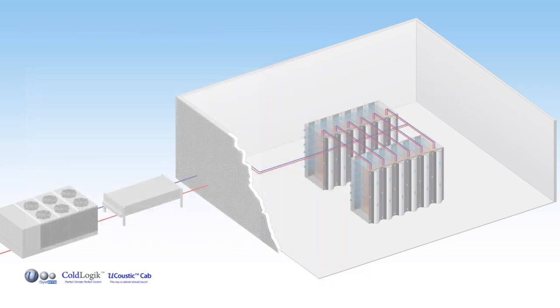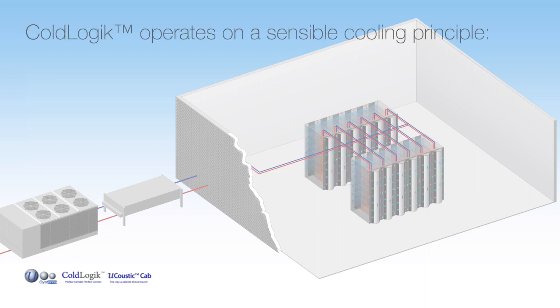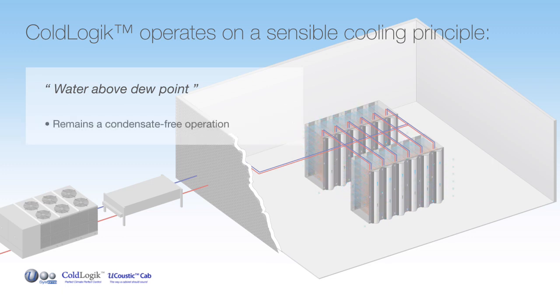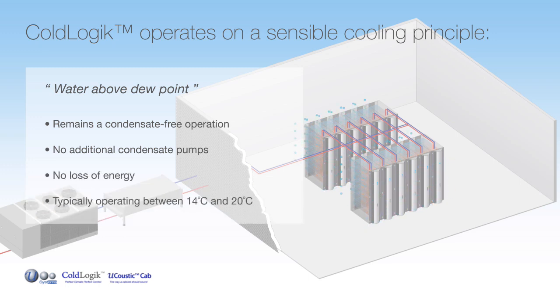The entire ColdLogik system operates on a sensible cooling principle, that is to say, water above dew point, ensuring that the system remains a condensate-free operation, so there are no additional condensate pumps and no loss of energy. Typically operating between 14 and 20 degrees Celsius, the CL20 family provides scalable cooling opportunities, offering duty up to 45 kilowatts. Although, with an 80 kilowatt cooler currently in testing, it is clear that USystems have both the present and future in mind.